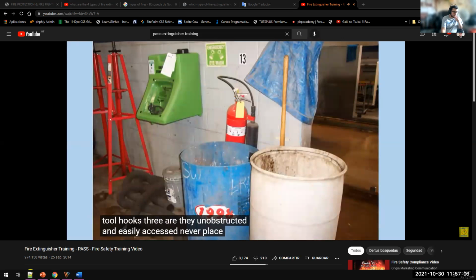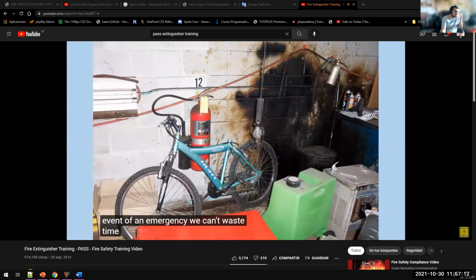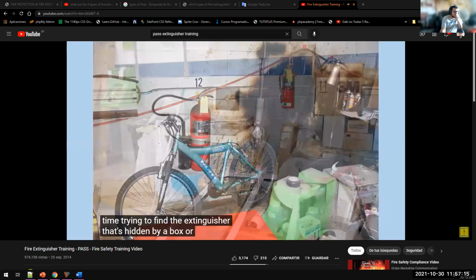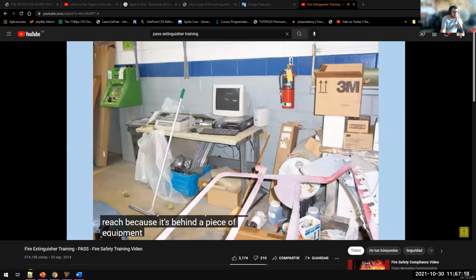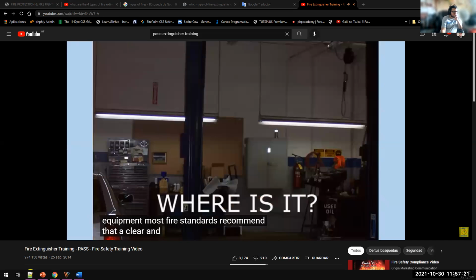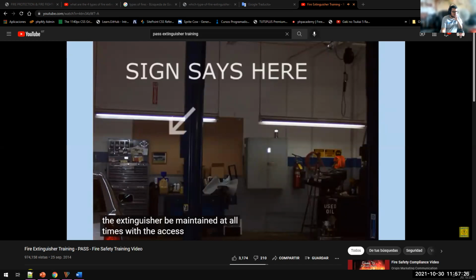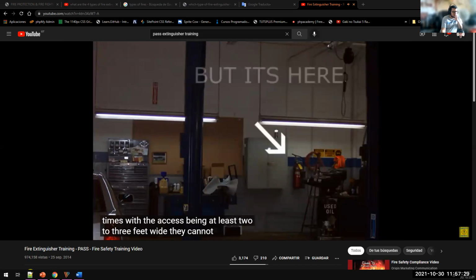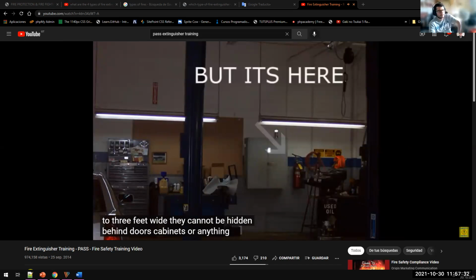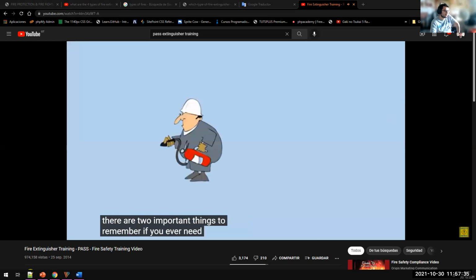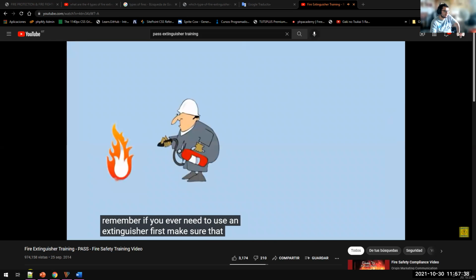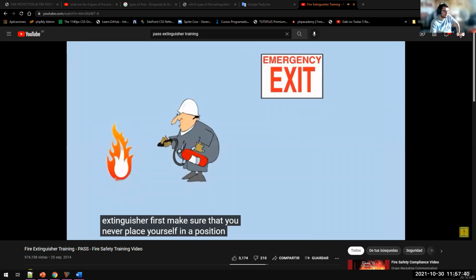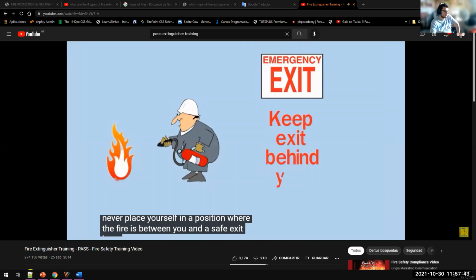3. Are they unobstructed? In the event of an emergency, we can't waste time trying to find the extinguisher that's hidden by a box or impossible to reach because it's behind a piece of equipment. Most fire standards recommend that a clear and unobstructed path to the extinguisher be maintained at all times, with the access being at least 2 to 3 feet wide. They cannot be hidden behind doors, cabinets, or anything else. There are 2 important things to remember if you ever need to use an extinguisher. First, make sure that you never place yourself in a position where the fire is between you and a safe exit. Keep the fire in front of you and the safe exit at your back.